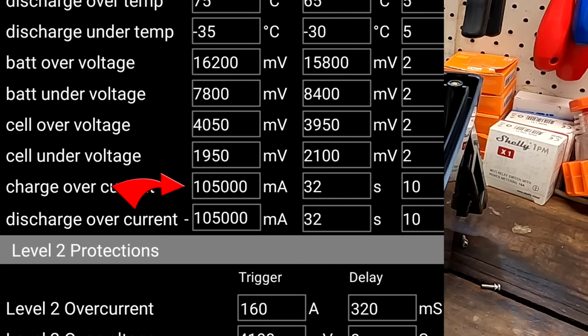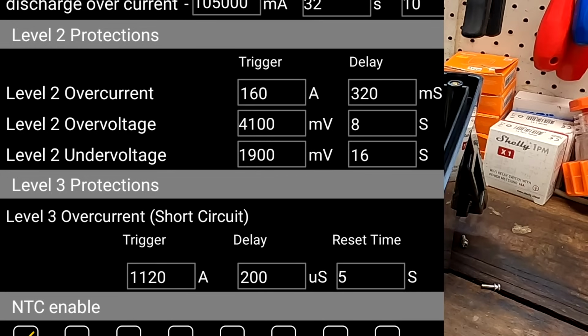And they've got a charge overcurrent of 105 amps. The battery says on the box here 50 amps is maximum. Why would you double that? And then we've got a level 2 protection of 160 amps, 4.1 volts over voltage and 1.9 under voltage, and also a 1120 amp short current trigger.